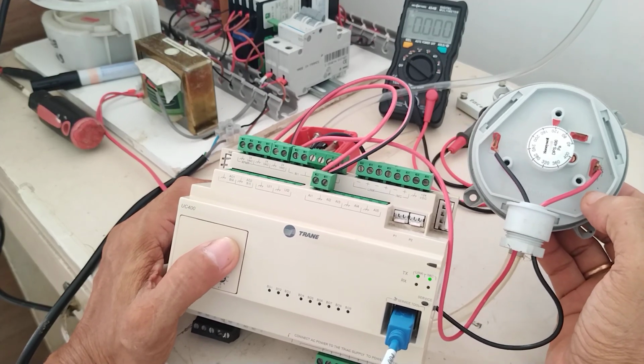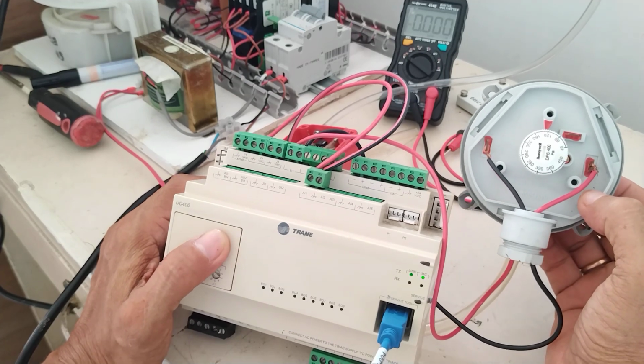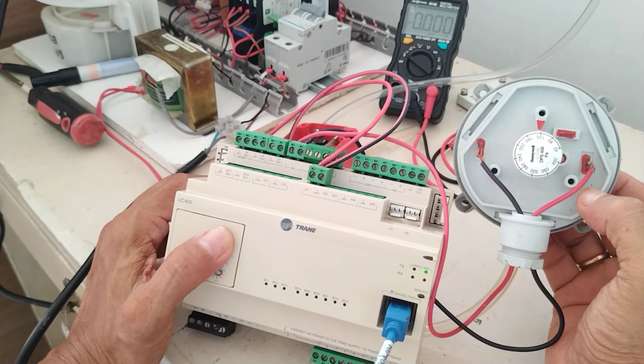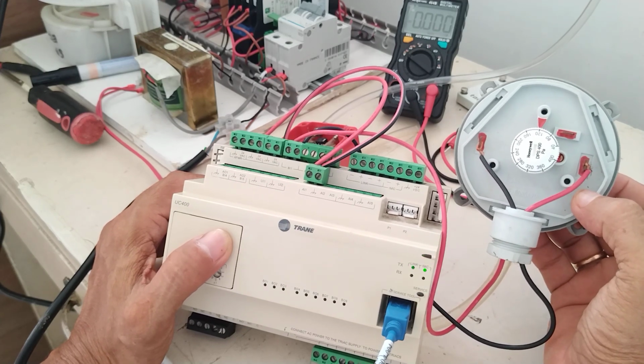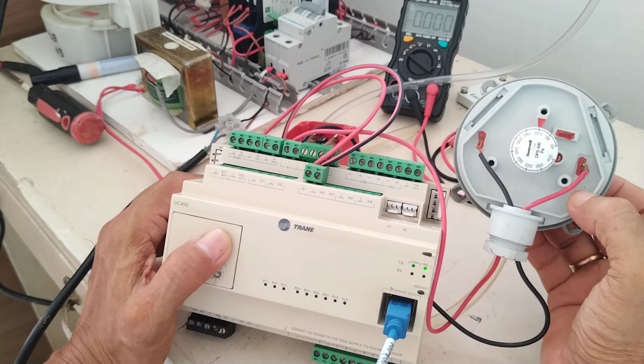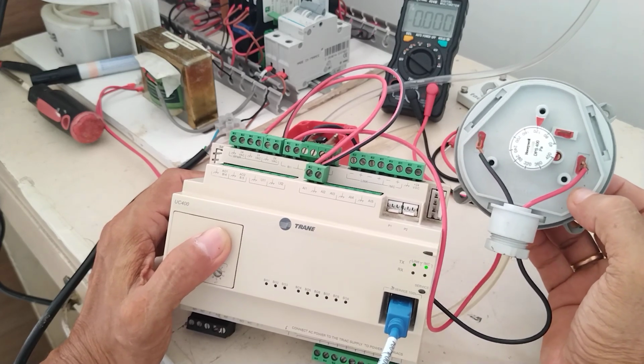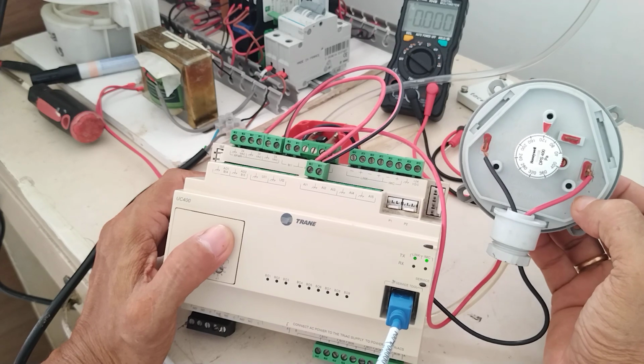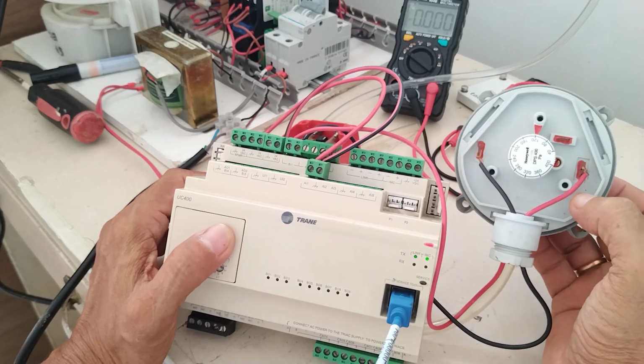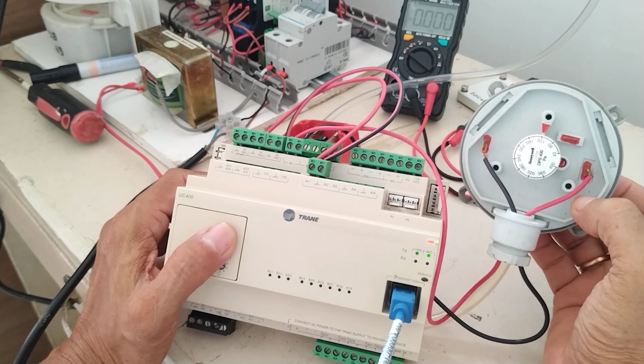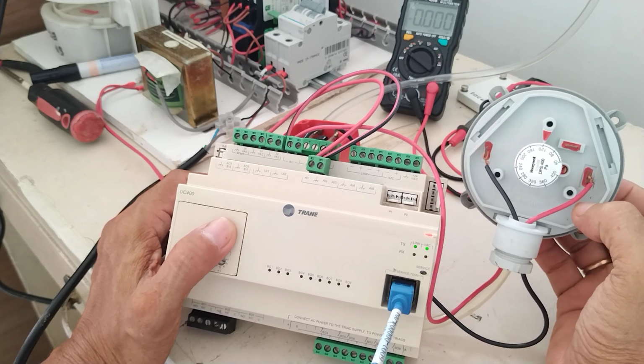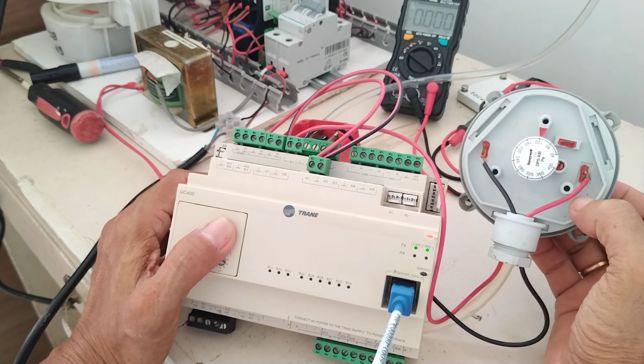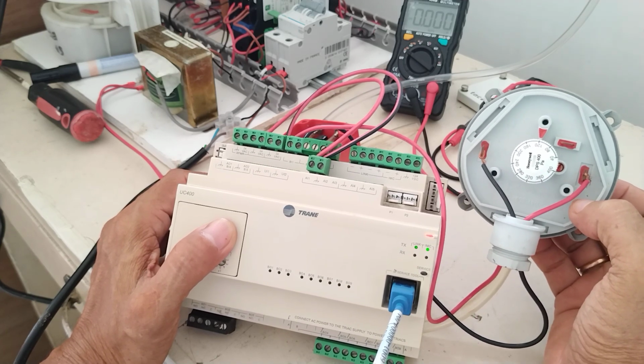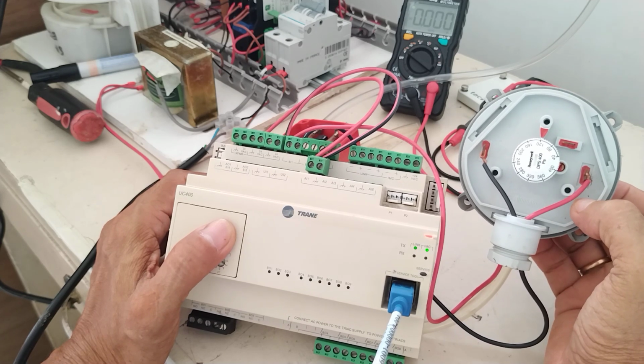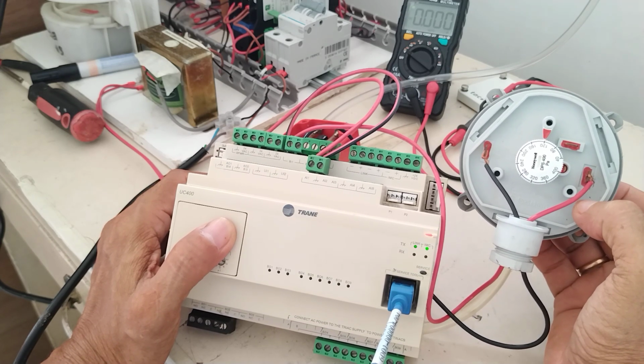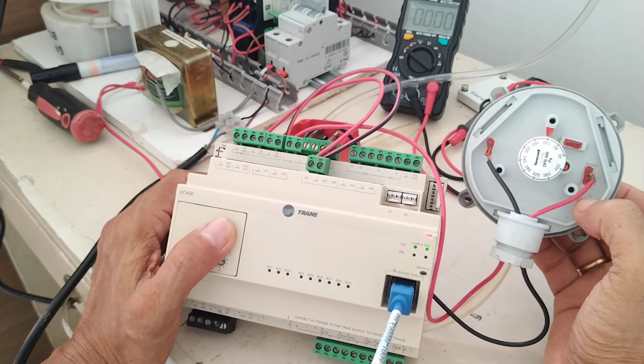Now, this is a big issue also in a project because if you don't do it properly, then you will be having problems, okay? Because these cables, especially these cables, are ordered from abroad. Let's say if you are in Qatar, maybe the cables will come from Dubai or other countries, or Turkey. Then, of course, there is some travel time. So you need to properly do the homework by doing the correct cable takeoff or the cable requirement of the project.